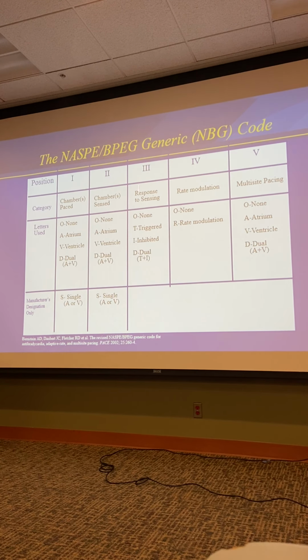So the mode we just talked about can be single or dual chamber, the lead configuration, unipolar and bipolar, we mentioned. These are the basic parameters that you'll see when they come out of the cath lab. The base rate, that's the lowest rate the heart's allowed to get to, most of the time. There are occasional situations where it can get lower than the base rate, and we'll talk about that in a minute. There's an upper tracking rate.